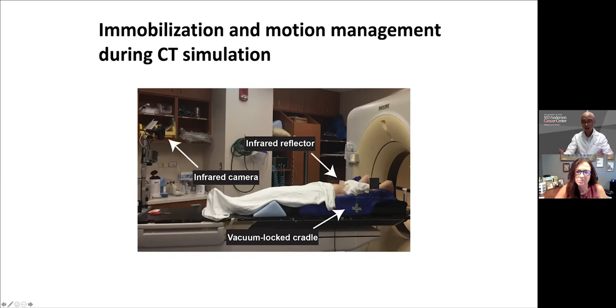And this is essentially the same setup as we have in the actual linear accelerator room. You can see this little cabinet here that has a laser, and you can see a little green laser beam actually on this side. We use that to localize, and kind of triangulate all of the body into the right position within the simulation room and translate that coordinate system over to the linear accelerator room where the therapy is actually delivered once the patient starts.